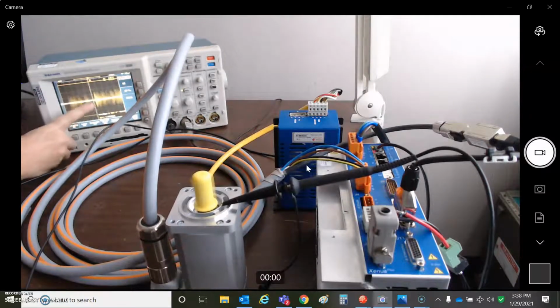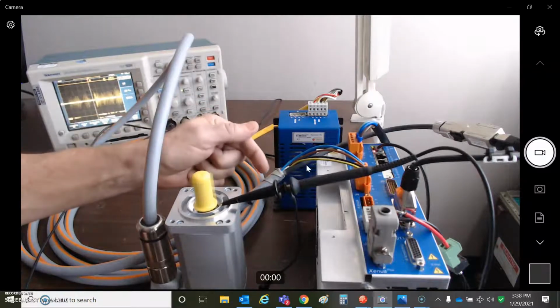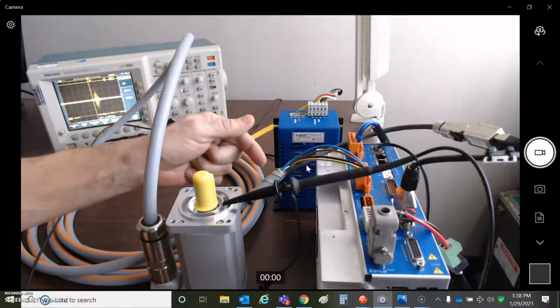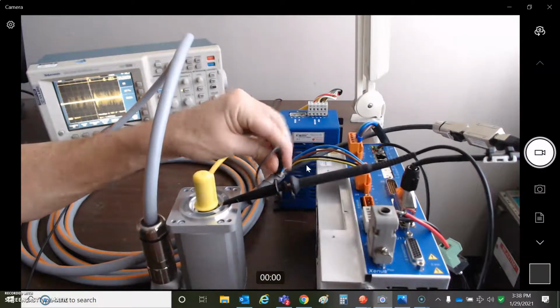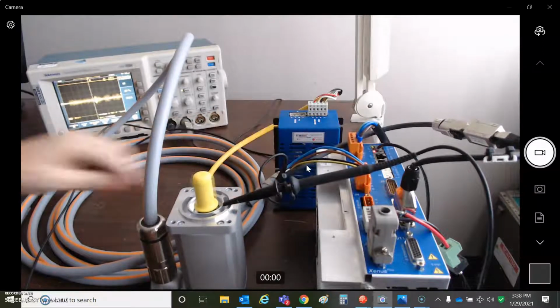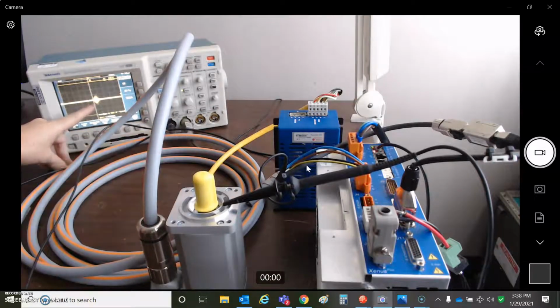And you can see the PWM switching noise here. I got 120 volts AC rectified and I got about plus or minus 40 volts peak to peak noise here. So that's an awful lot of noise. This is the outer shield that's supposed to be bonded at the drive to earth. So I'm just gonna hook up my little scope probe ground here. And you can see just by connecting the outer shield to earth, I got plus or minus 20 volts of PWM switching noise. Okay, and this allows the system to run a lot more reliably without any errors, less CRC faults, that's for sure. But the system seems to run much better by grounding this.